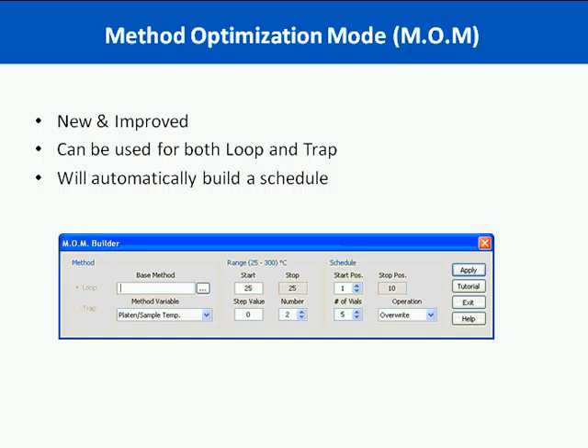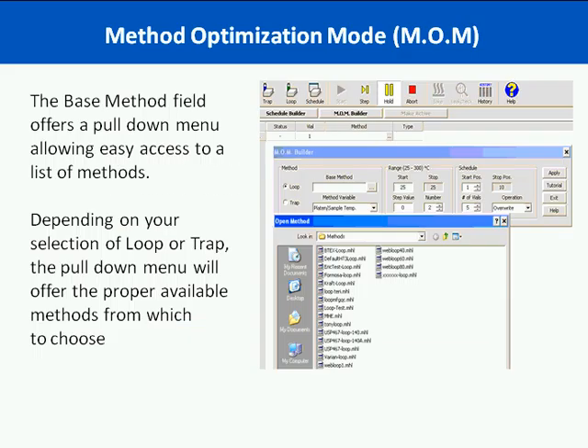When trying to do your scheduling or method development work, it can be tedious if you're thinking of all the method parameters you want to vary to fine-tune your instrument. However, with the HT3, method parameter optimization can be performed quite easily through the use of our Method Optimization Mode, often referred to as the MOM of the HT3. This is a new and improved feature that can be used for both loop and trap modes — static or dynamic — and can be used at the same time within a single schedule. If you're doing initial method development and not sure whether to do static or dynamic, you can choose both, vary those method parameters, and build one single schedule.